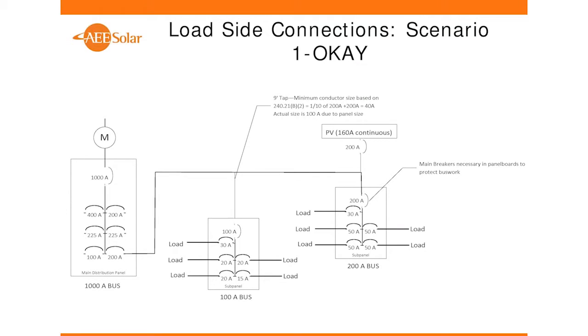So let's look at that. Going back to the same diagram here, we've got this tap here. By definition, the tap overcurrent device is not at the tap location, where it taps into the feeder. It is 10 feet away from that location. That's allowed. And the size of this tap conductor can be no less than 1/10 of the feeder breaker. That's the normal way. So if we take PV out of it, let's just say the PV is not in the circuit at all, then the minimum size of this tap conductor would be 20 amps. That would be the minimum size before even looking at loads.